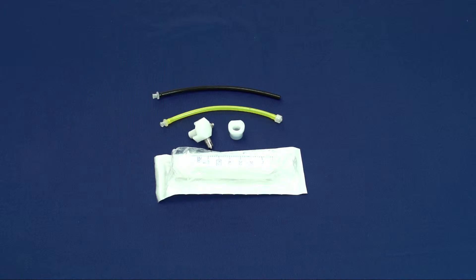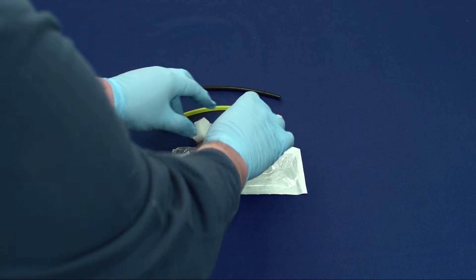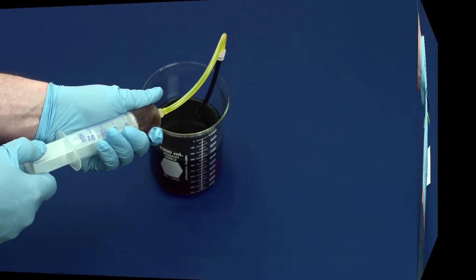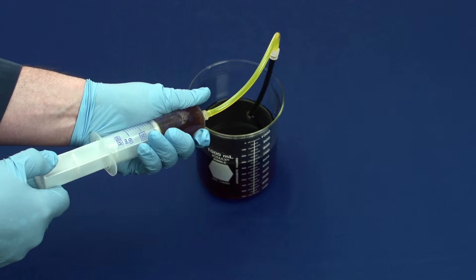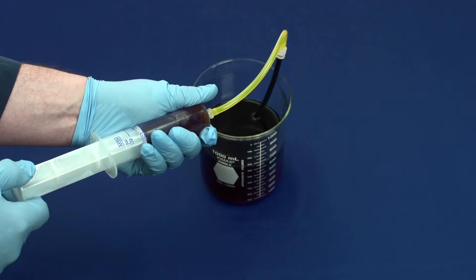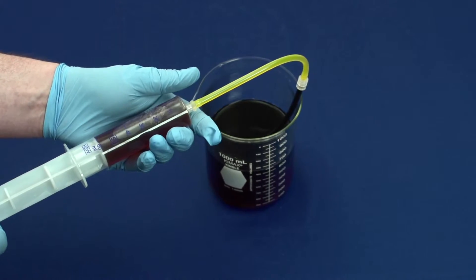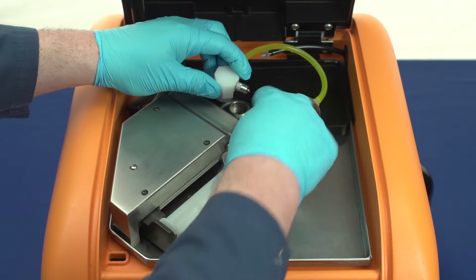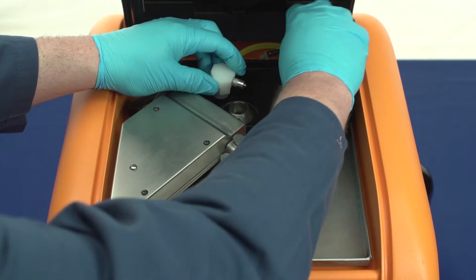To prepare to use AccuFlow technology, simply assemble the AccuFlow kit provided for your XOS benchtop analyzer. After you assemble the syringe, draw back the syringe's plunger and take in your crude oil sample into the syringe. After opening the lid to the analyzer, place the filled syringe inside and lock in place.